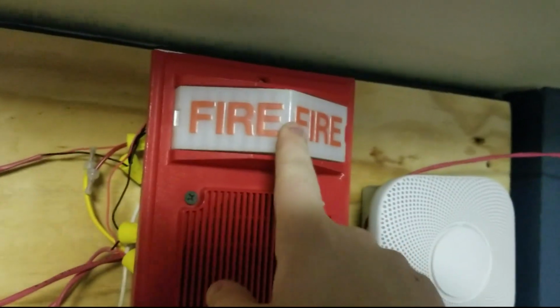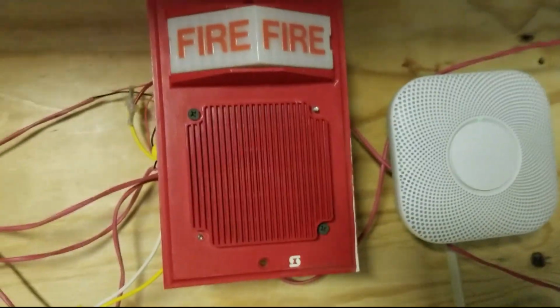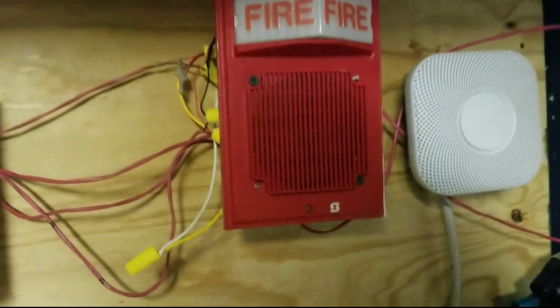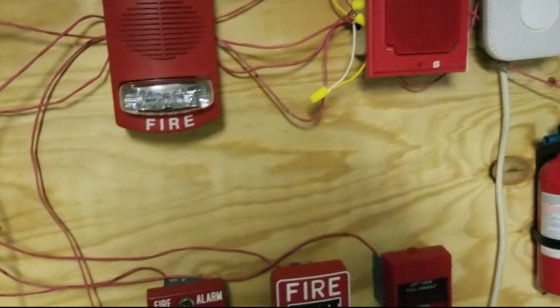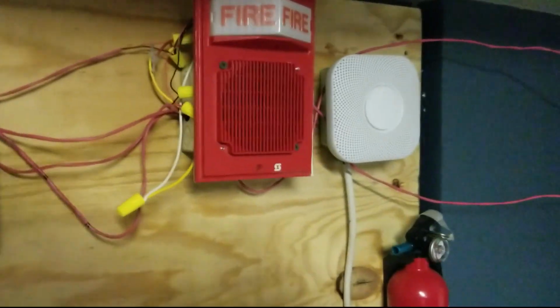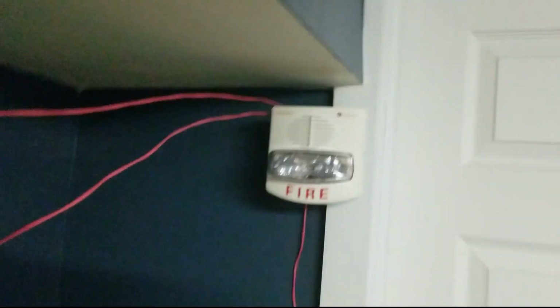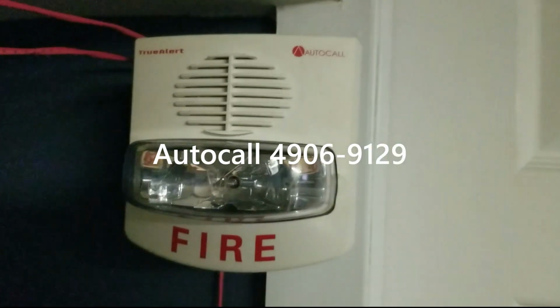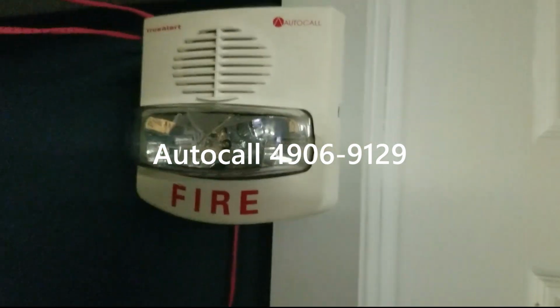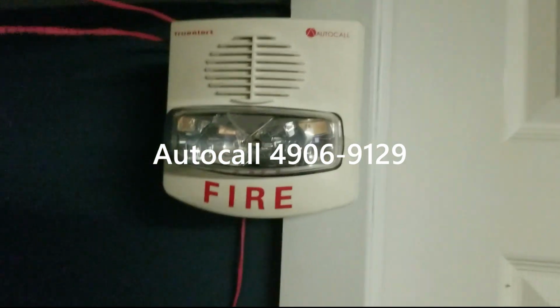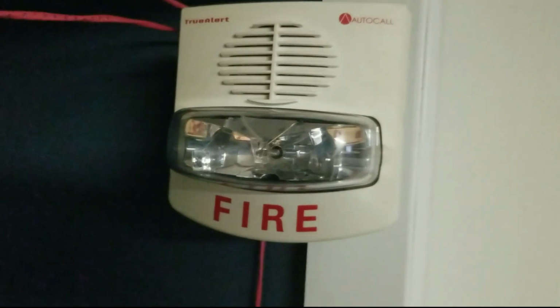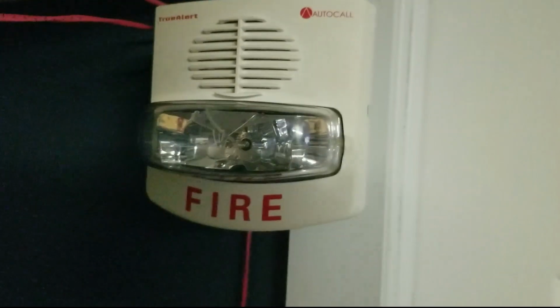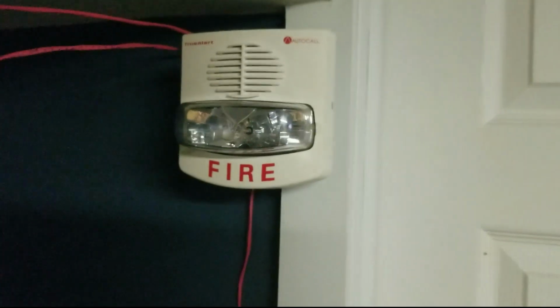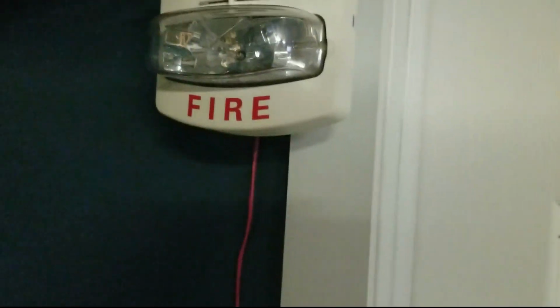And this is on NAC 4 because it's going to be coded to do a march time flash, but it's also not going to stop when I hit the alarm silence button. So it's not going to silence. And then for the notification appliance over here, I still have the True Alert horn strobe 2-wire, and it's on NAC 3. NAC 3 is currently set to strobe only though, so this is not going to do any horns. It's just going to be the strobe.